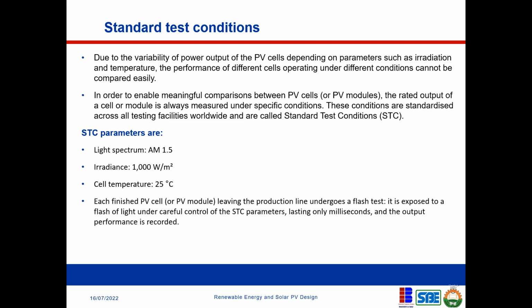Each finished PV cell or PV module leaving the production line undergoes a flash test. It is exposed to a flash of light under careful control of the STC parameters, lasting only milliseconds, and the output performance is recorded.